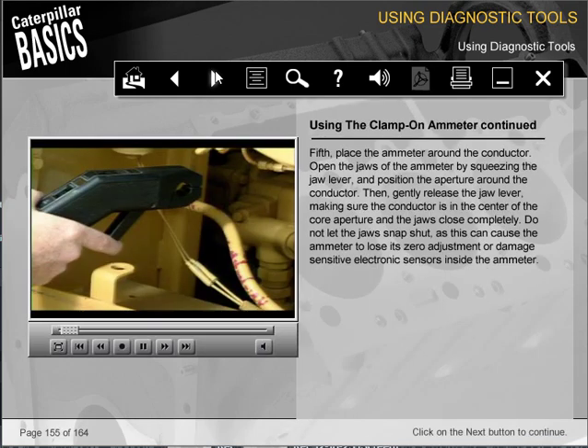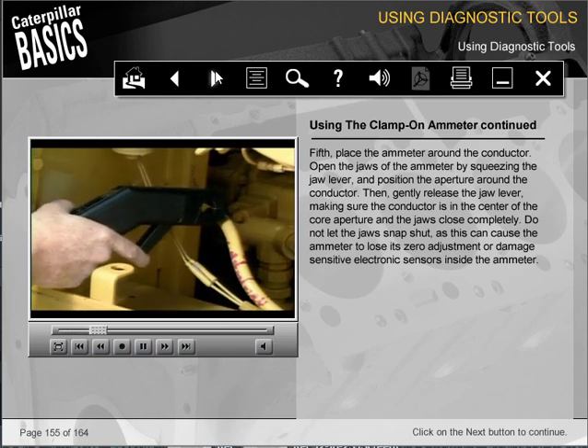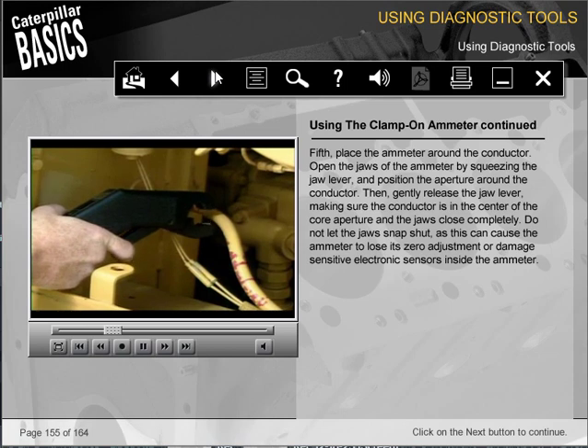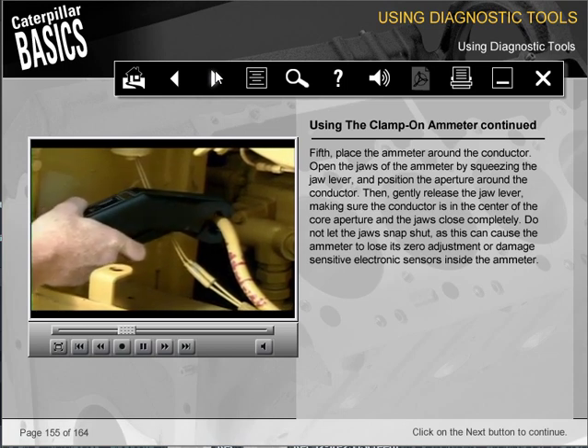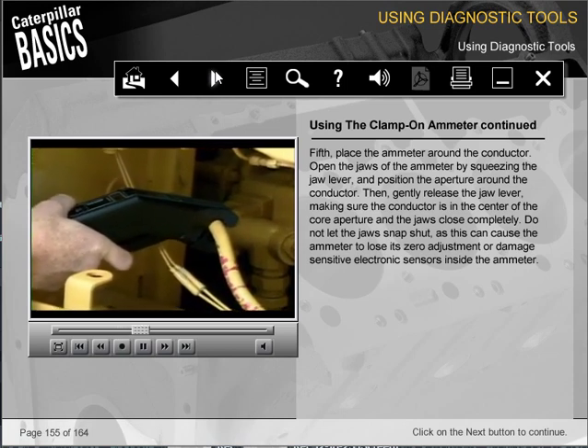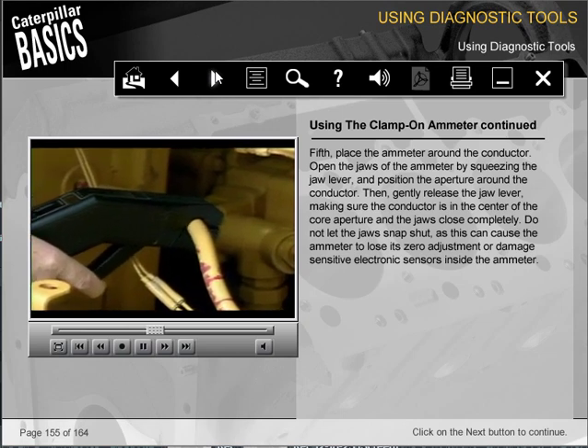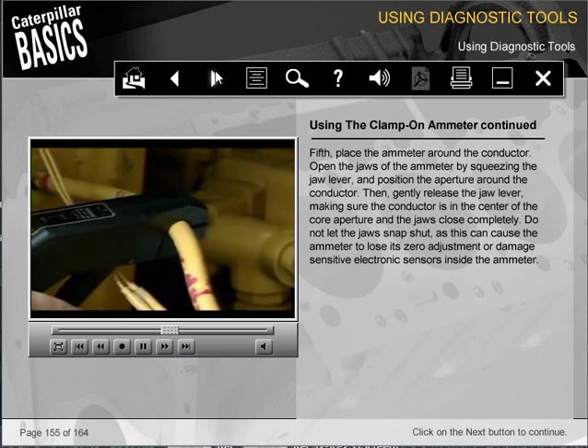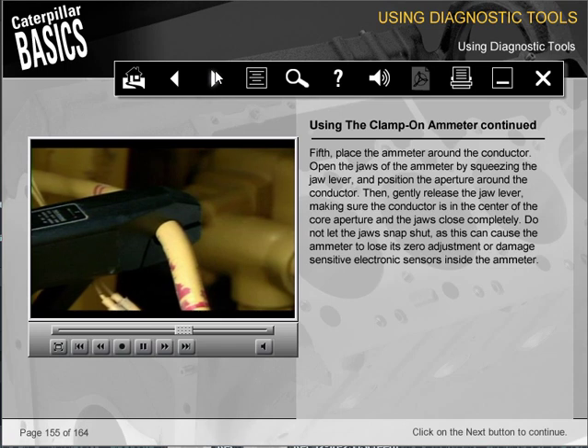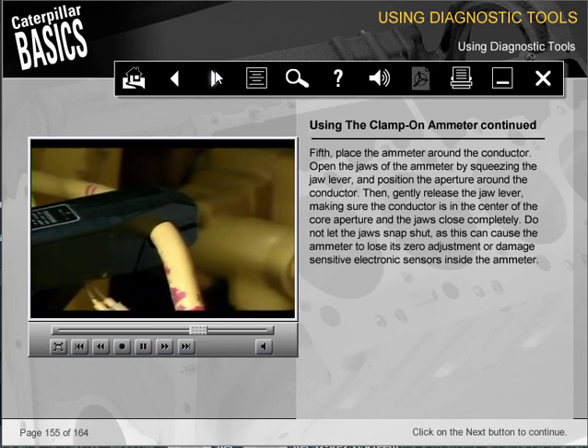Fifth, place the ammeter around the conductor. Open the jaws of the ammeter by squeezing the jaw lever and position the aperture around the conductor. Then gently release the jaw lever, making sure the conductor is in the center of the core aperture and the jaws close completely. Do not let the jaws snap shut, as this can cause the ammeter to lose its zero adjustment or damage sensitive electronic sensors inside the ammeter.